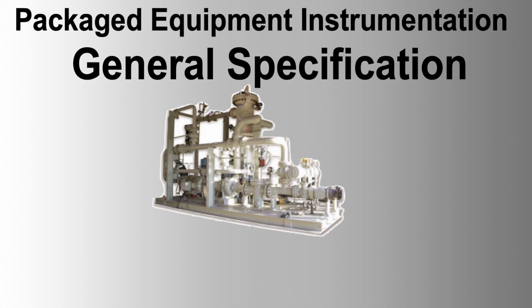Cable trays must allow access to equipment and avoid blocking walkways, with 0.5 meter separation between cable groups where possible. Perforated steel or aluminum trays should be used, with a minimum of 25% spare capacity for future installations. Earthing and bonding: earthing conductors should be stranded and insulated, with separate bars for safety and instrumentation earths, and appropriate bonding for metallic instrumentation enclosures.